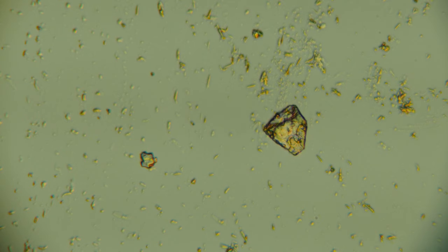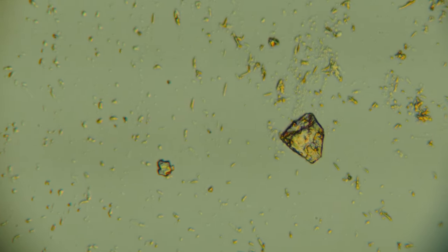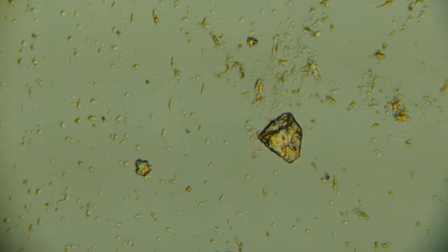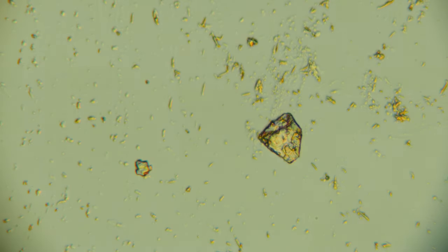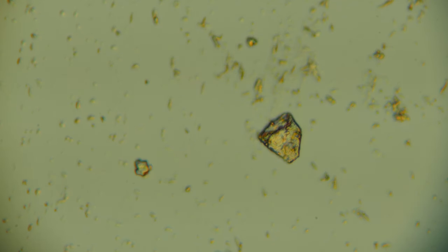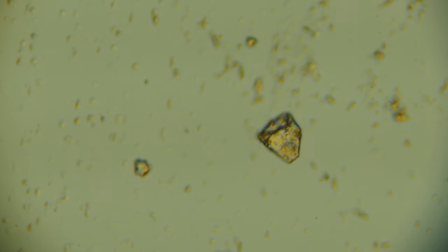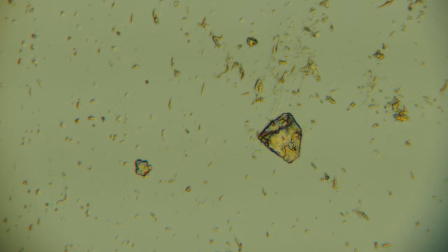Here we are without the projection eyepiece. I think I was having some problem with my condenser being a little bit too closed, which makes it look a little like that. But with the condenser reasonably open, here's the 40X — we're seeing detail. So something tells me that maybe that projection eyepiece is causing the problem. Here's the 40X DIC with the correct 40X prism below, and we can see different layers of it pretty clearly.